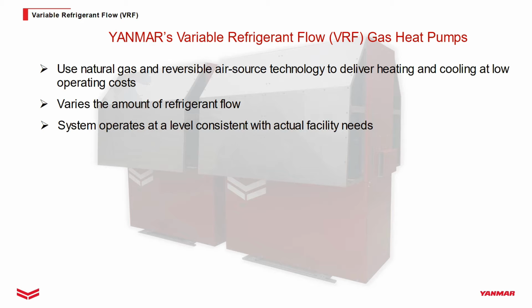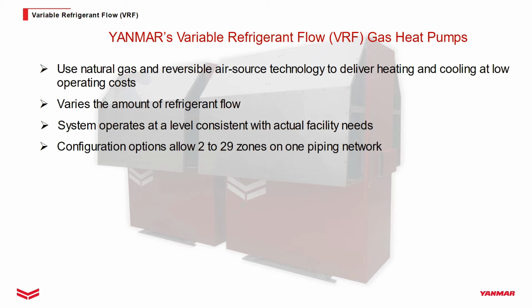Users can create zoned comfort depending on the needs of the building. Configuration options allow for as few as 2 zones and up to 29 zones on a single piping network. With a heat recovery option, buildings can be heated and cooled simultaneously in different zones or different rooms within that facility. This means one room or zone can be heated at 80 degrees, while another room or zone can be cooled at 65 degrees simultaneously from the same condensing unit.